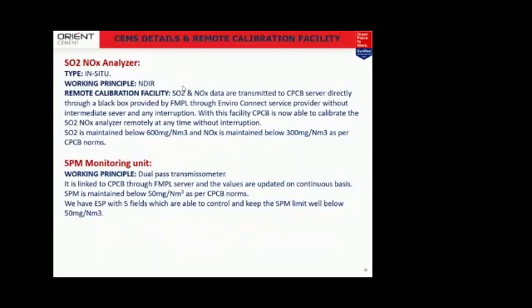Next, coming to the CEMS details and the remote calibration facility that we have here in the Chitapur plant, in the captive power plant. The SOx NOx analyzer we are using is of Forbes Marshall make, and it is a very unique one. It is an in situ type, not the extractive type of component, and it works on NDIR technology, that is the non-dispersive infrared principle.